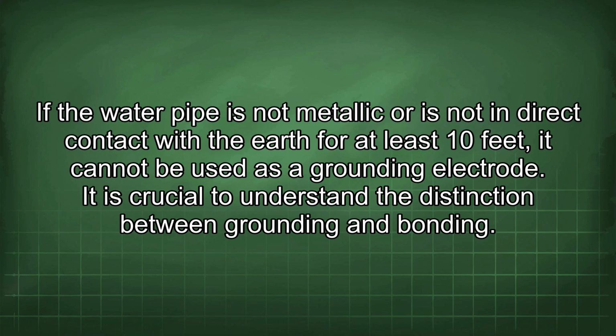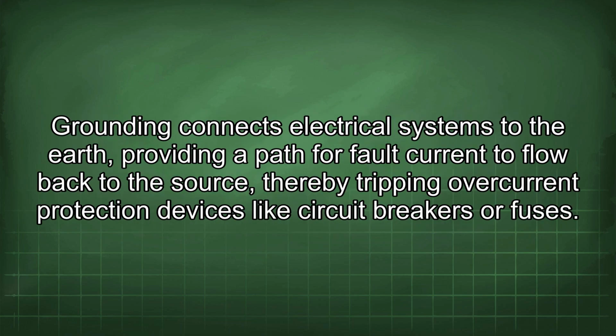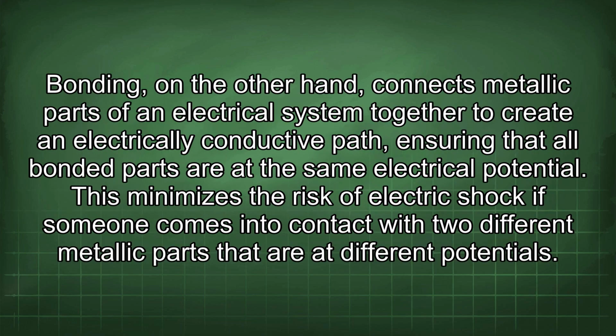It is crucial to understand the distinction between grounding and bonding. Grounding connects electrical systems to the earth, providing a path for fault current to flow back to the source, thereby tripping overcurrent protection devices like circuit breakers or fuses. Bonding, on the other hand, connects metallic parts of an electrical system together to create an electrically conductive path, ensuring that all bonded parts are at the same electrical potential.